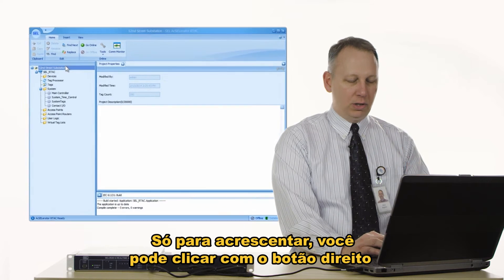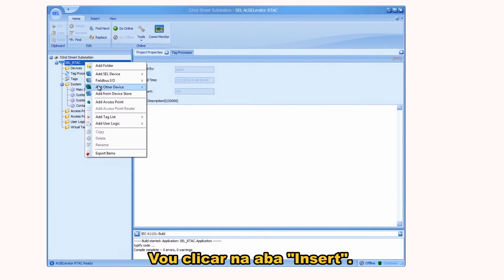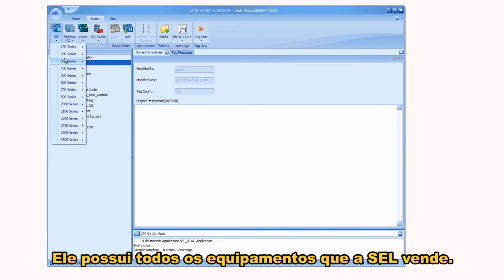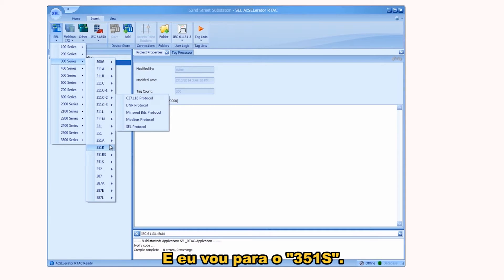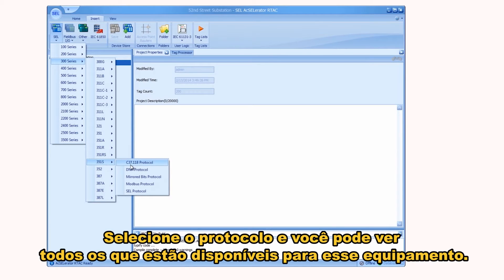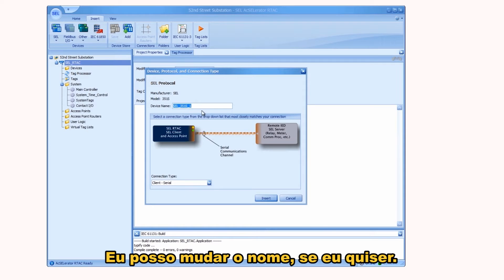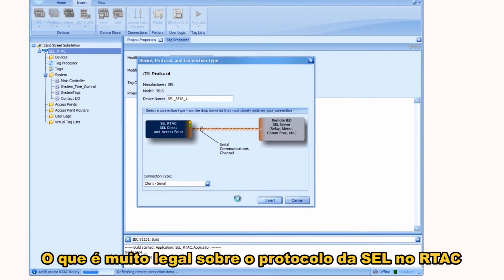We're going to click on the Insert menu. As a side note, you can also right-click anywhere in the device tree to add devices. I'm going to click on the Insert ribbon, select SEL — because that's the kind of device I want to add — and it shows all of the SEL devices that SEL sells. I'll go down to 351S, select the protocol. You can see all the protocols available for that device. I want to select SEL protocol, and I can change the name, select serial or Ethernet, then click Insert.